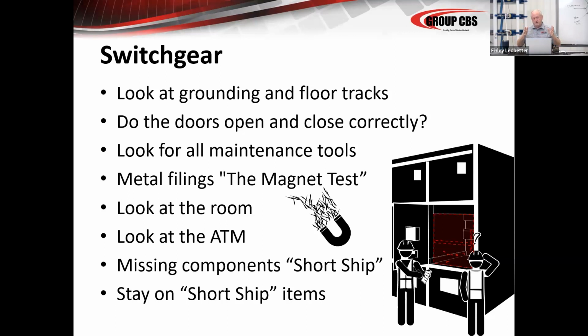If the doors on the switchgear do not open and close correctly, I guarantee you're going to have problems inserting and removing the breakers, and it's just going to get worse. Normally there's a leveling pad underneath the switchgear, and the switchgear is built on an I-beam, so it should all be nice and square. Be sure that the doors open and close correctly. There's proper gaps around it. If there's not, question it.